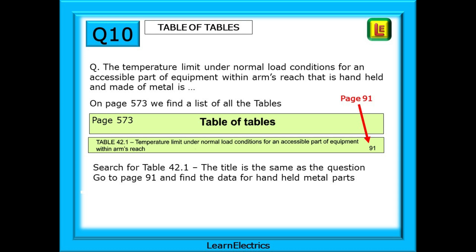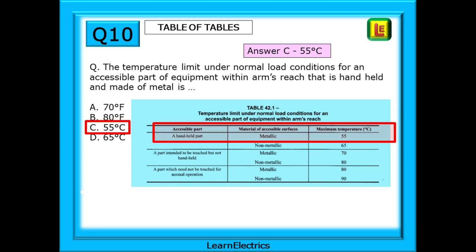And find the data for handheld metal parts. Here we are on page 91 and table 42.1 is shown. Looking at the table we can follow the top line for handheld and for metallic parts and it shows that the maximum temperature should not exceed 55 degrees centigrade and we should choose answer C.